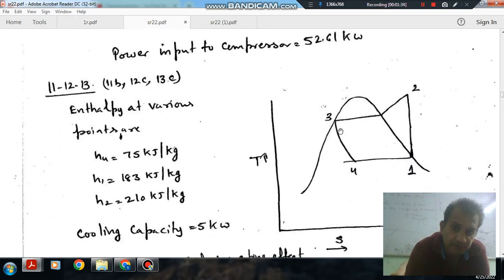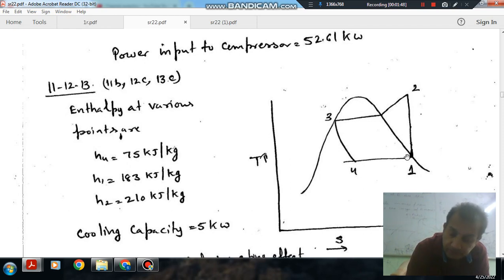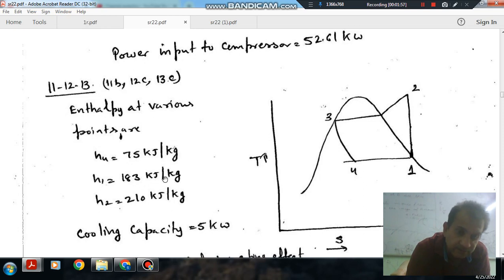The enthalpy at various points: H4 is 75 kJ/kg, which is the enthalpy at the entrance of the evaporator. When the refrigerant leaves the evaporator the enthalpy is H1, that is 183 kJ/kg. At the exit of the compressor the enthalpy is H2, that is 210 kJ/kg. The cooling capacity is 5 kW.